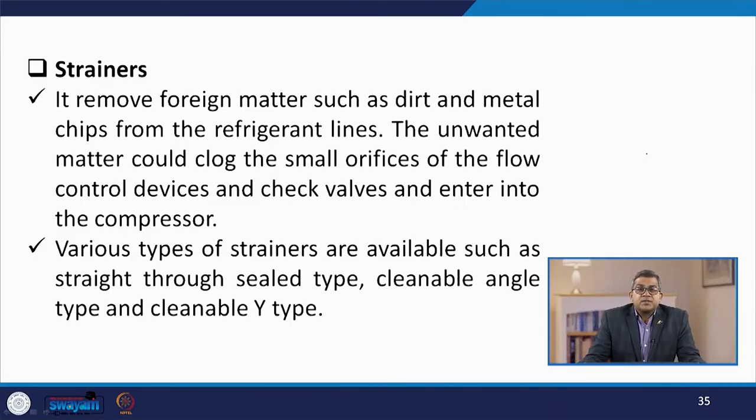Over the period of circulation of refrigerant in the piping system, the refrigerant may accumulate certain types of dirt, dust, and debris due to metal chip removal, corrosion, or problems in the internal lining. The basic purpose of a strainer is to remove foreign matter like dirt and metal chips from the refrigerant line, as unwanted matter can clog the small orifice of the flow control device, throttling device, check valves, and enter into the compressor. Various types of strainers are available, such as straight-through seal type, cleanable angle type, and cleanable Y type.